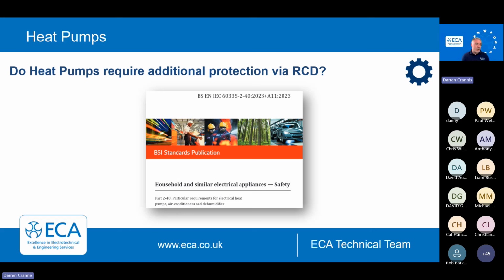Importantly, heat pumps are covered by their own product standard, and they fall into BS EN IEC 60335-2-40. Quite a mouthful. It's an international standard, so it's written for the whole world. Guidance from the heat pump associations is typically based on domestic installations, and there are some circumstances where a circuit supplying a heat pump may not need RCD protection. Heat pumps are not a special location by themselves. They're not in the back of the book. They're not a Part 7. So normal BS 7671 rules apply.